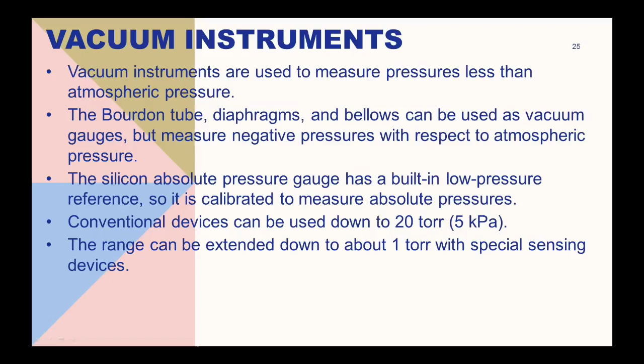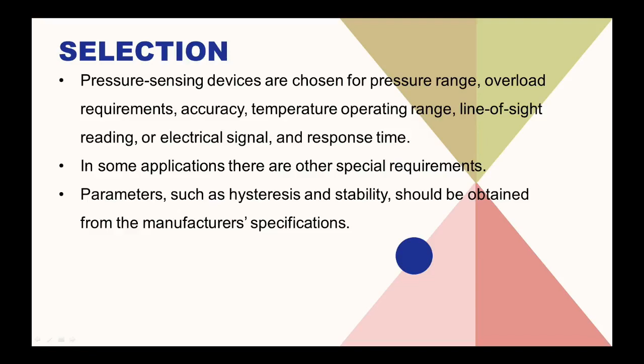Application consideration. When installing sensors, care should be taken to select the correct pressure sensor for the application. So ano ba yung mga dapat natin consider? So first, selection. Pressure sensing devices are chosen by the pressure range, overload requirements, accuracy, temperature, operating range, line of sight reading, or electrical signals, and response time. In some applications, there are other special requirements. Parameters such as hysteresis and stability should be obtained from the manufacturer's specification. Hysteresis, parang ito yung value ng physical property na naglalag behind.